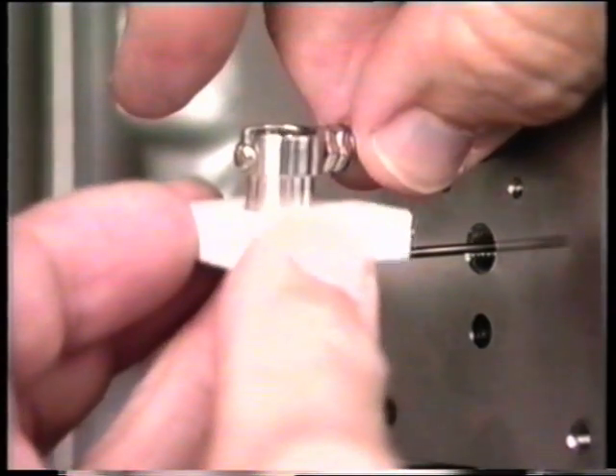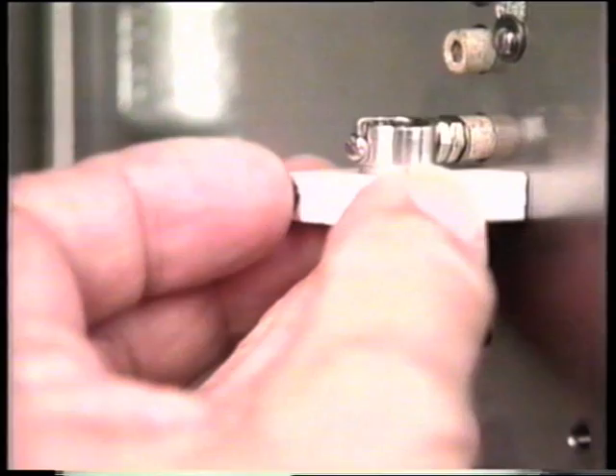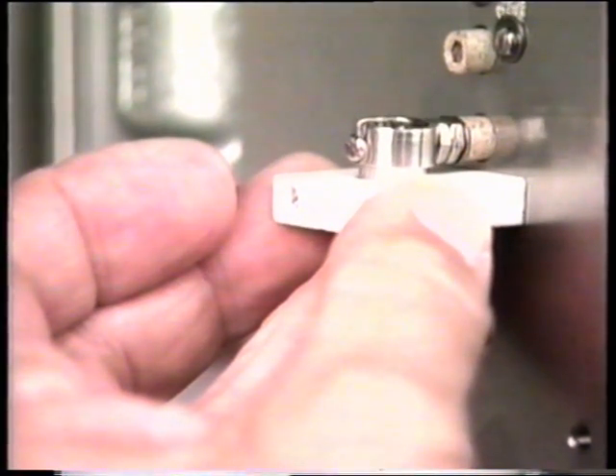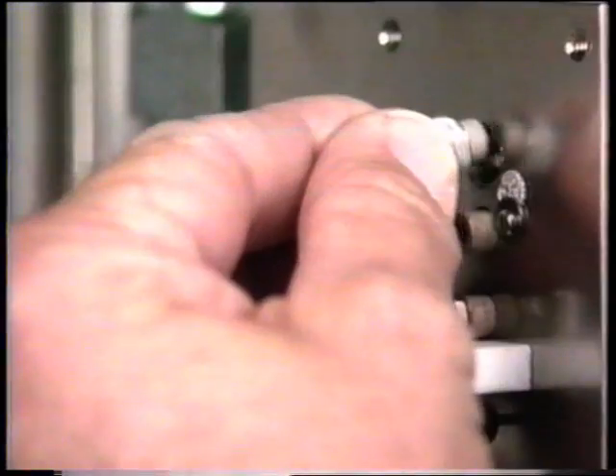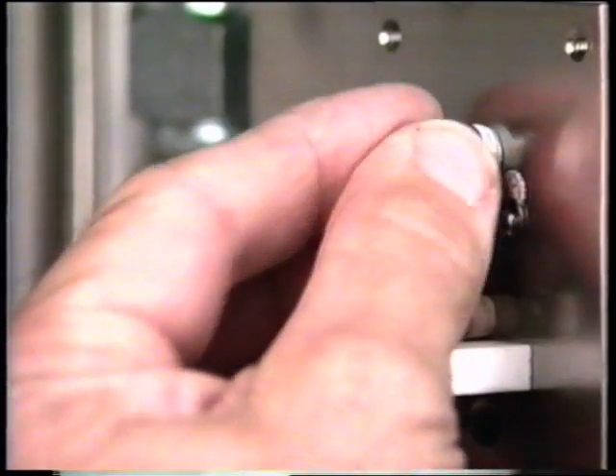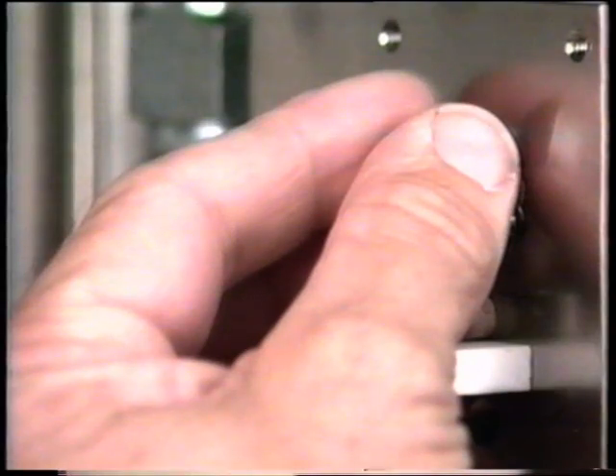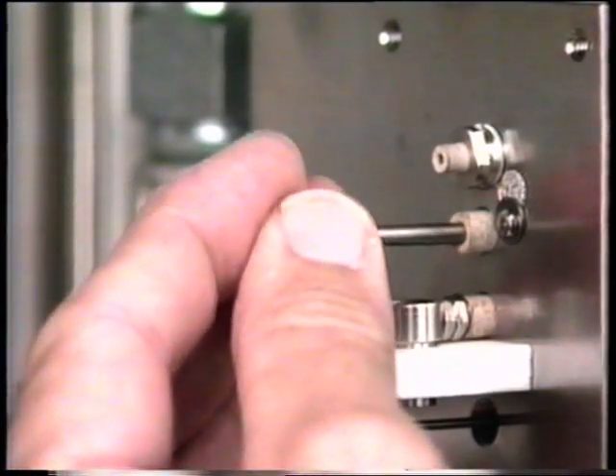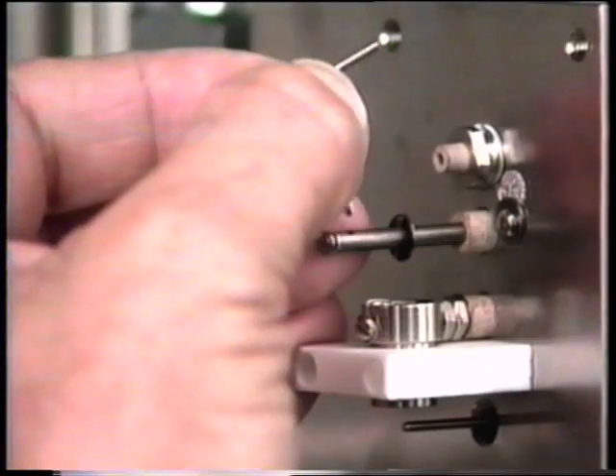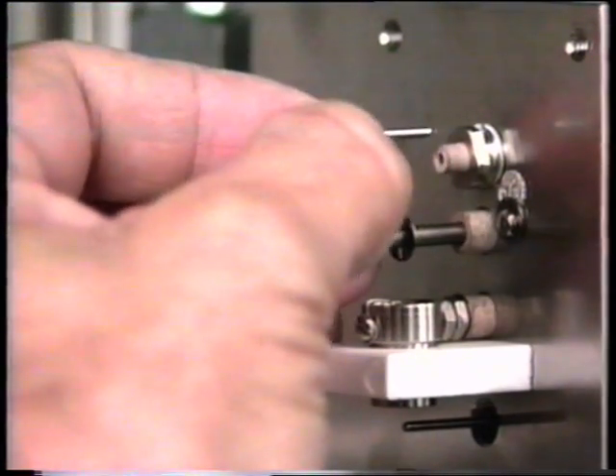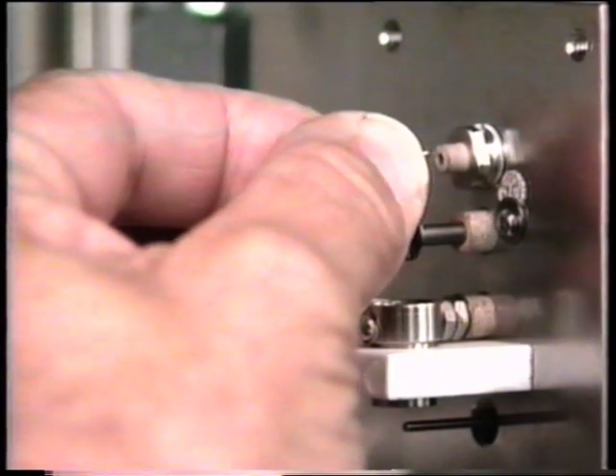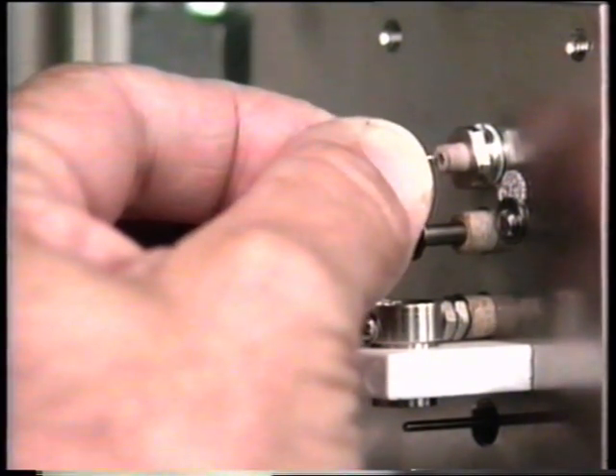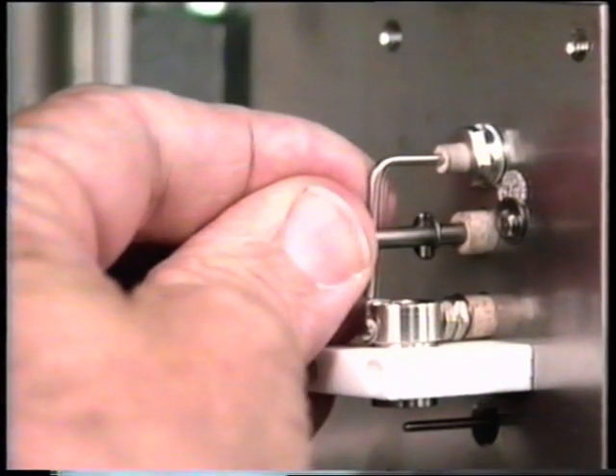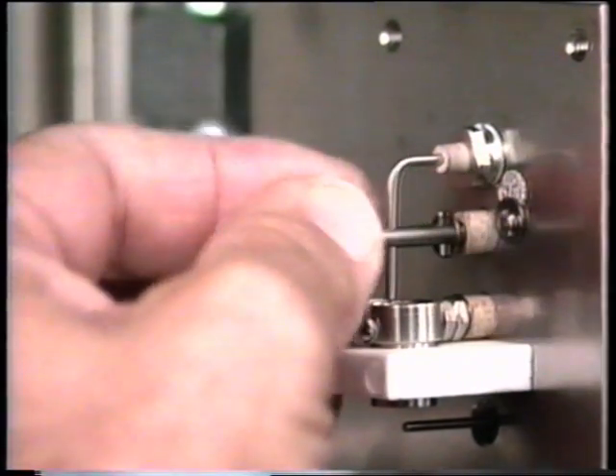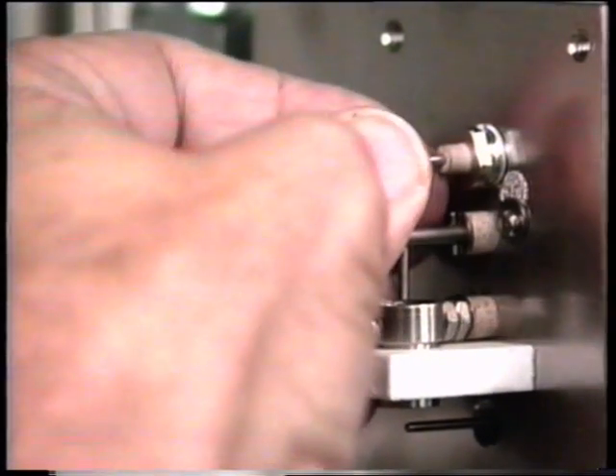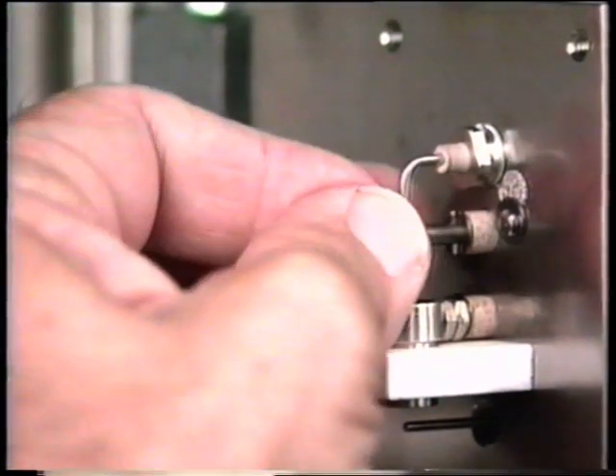Place the baffle plate against the body and slide it over the bottom portion of the collector until the baffle plate holes align with the threaded holes of the body. Place the burner tip ferrule in its cavity and loosely fasten it in place. Insert the bias ignite electrode partway into its insulator. Insert the long end of the burner tip through the hole in the electrode. Align the short end of the burner tip with the hole in the end of its ferrule. Push the burner tip and the bias ignite electrode toward the body until the long end of the burner tip is centered over the collector and the short end is pushed into the ferrule.